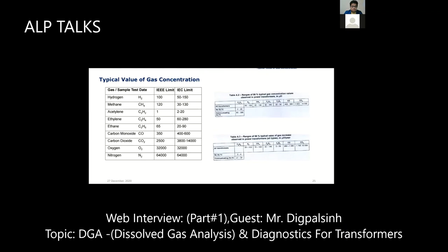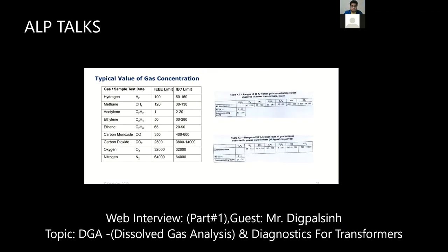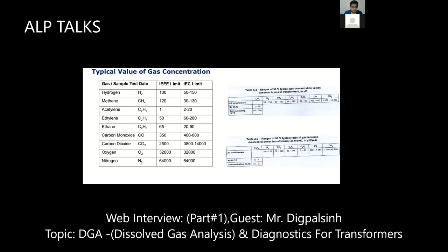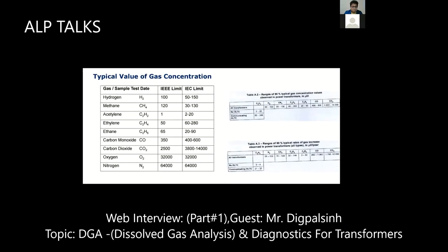These are the typical values of gas concentration for a healthy transformer, or you can say a 1 or 2 year old transformer. This limit is given by two different standards, IEEE C57.104 and IEC 60599. So hydrogen is 100 ppm, and the unit for the limit is ppm.